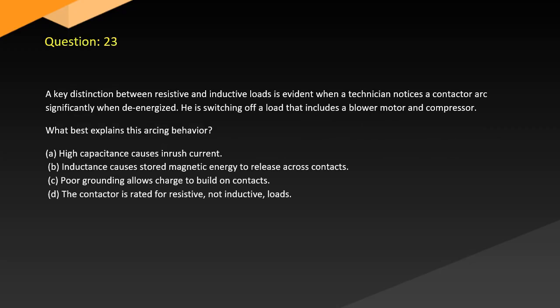Question 23. A key distinction between resistive and inductive loads is evident when a technician notices a contactor arc significantly when de-energized. He is switching off a load that includes a blower motor and compressor. What best explains this arcing behavior? A. High capacitance causes inrush current. B. Inductance causes stored magnetic energy to release across contacts. C. Poor grounding allows charge to build on contacts. D. The contactor is rated for resistive, not inductive loads.